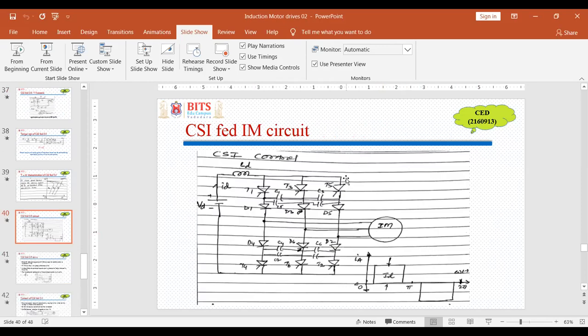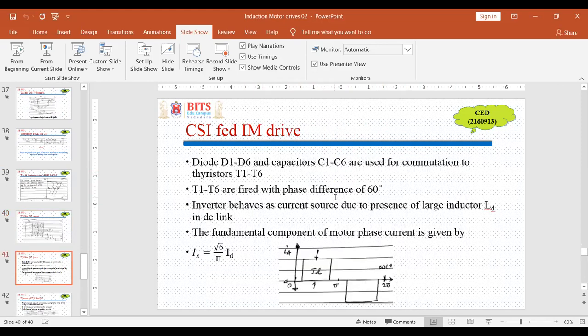This is the circuit for CSI-fed induction motor drive. We can see that thyristors are used with diodes and capacitors for turning off the thyristors, and a large inductor Ld is used in series with the DC voltage source so that it can be converted into a current source. These are the various features we have already discussed in yesterday's class.